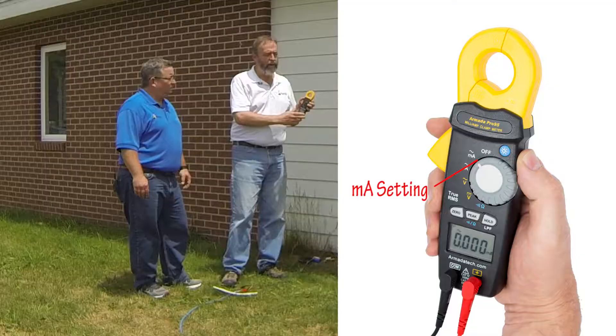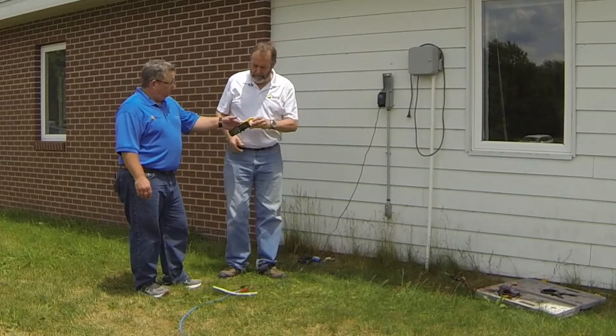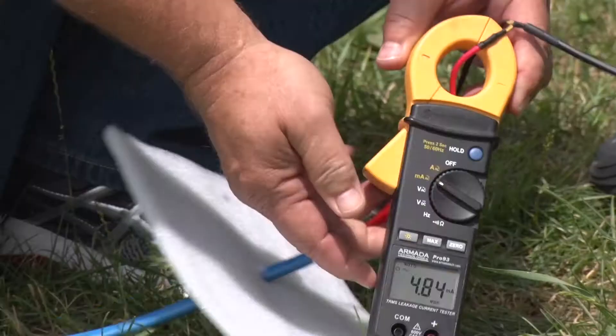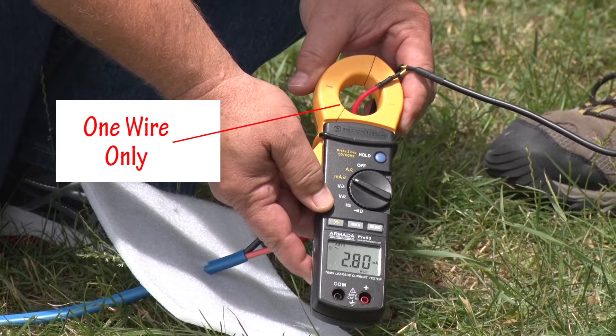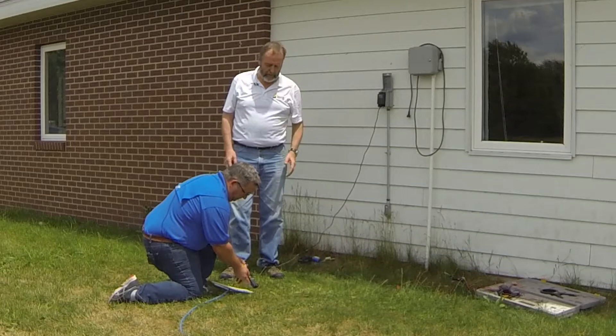What we're going to do first is turn the meter to the milliampere current setting, which means that the jaws will now be measuring very small levels of current. At the head end of the cable, disconnected from the controller, we check the leakage current. We always clamp across one wire, not both wires, because this current is looping out into the field. We're reading about 2.8 milliamperes, which is the sum current of these two Rainbird decoders out here — that is a normal situation.